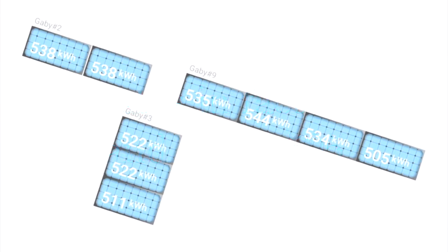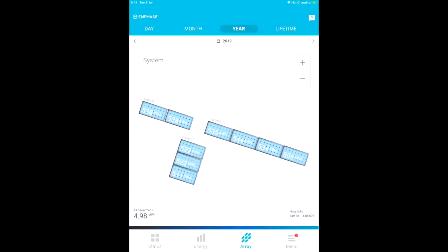Now, there's a reason for this, and this is one of the reasons in this particular install that we insisted on using microinverters, because we knew, because of the complexities of their roof, there were some shading issues. This is totally fine.